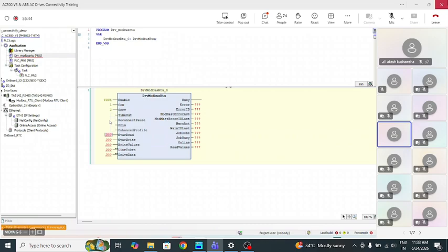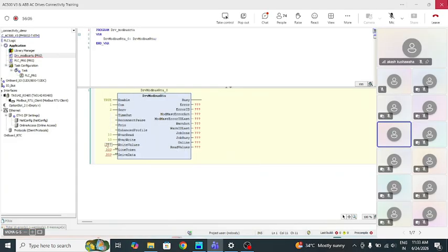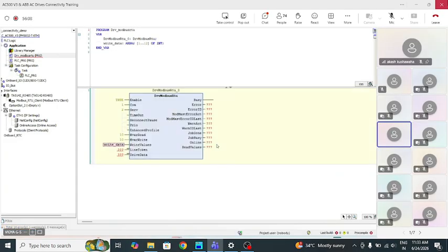Then if you're using enhanced profile, then this NVar read, NVar write will be applicable. So you can enter how much data you want to read and write. You can enter like 10, 10. Then write values, so you can give a name for this. This is if you want to write any values to the drive. Then, which we discussed in the out parameter, line token.